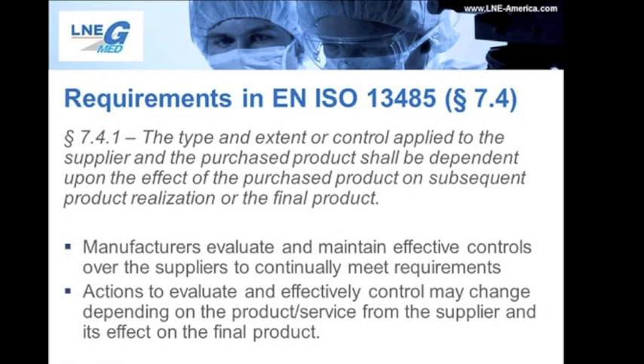Section 7.4.1 also states that the type and extent of control applied to the supplier and the purchased product shall be dependent upon the effect of the purchased product on subsequent product realizations or the final product. So in other words, in making up the procedures to ensure that the product conforms to the specified requirements, the manufacturer should consider the importance of the product or service to the device's regulatory conformity and safety.